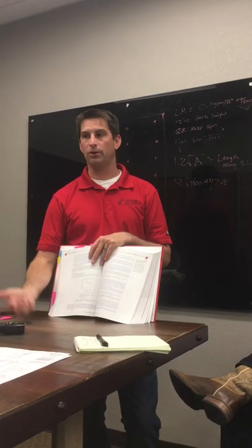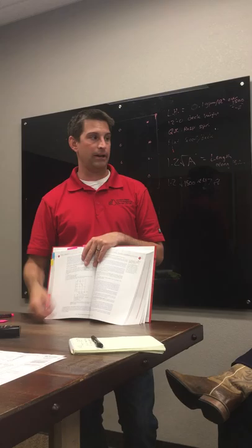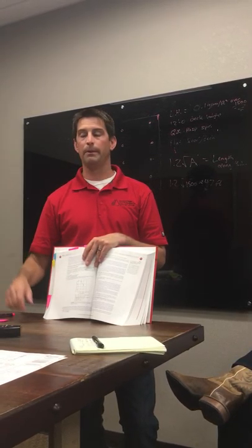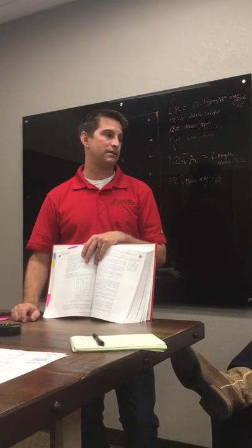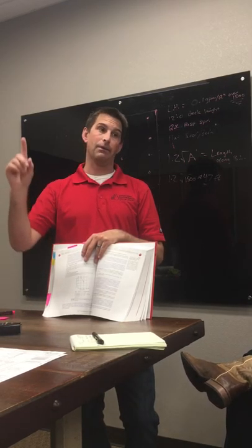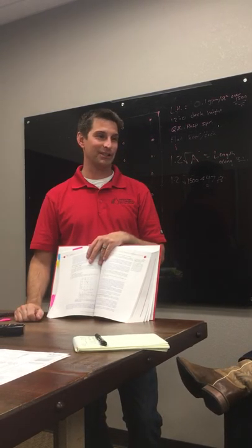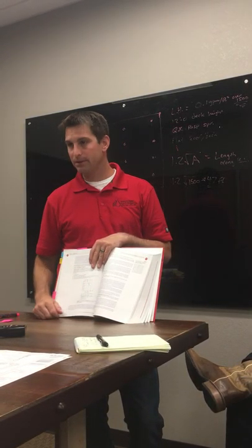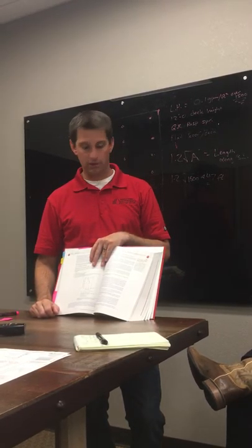I saved one sprinkler, but now I didn't get the quick response reduction, and all the pipe in my whole building is 2 pipe sizes bigger than it needs to be because of that one sprinkler I saved. So don't do that. Sometimes you want to just include it.